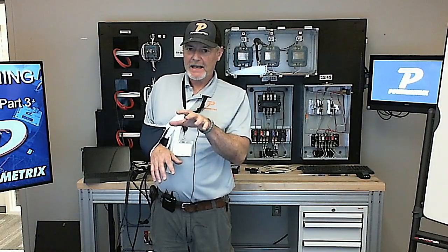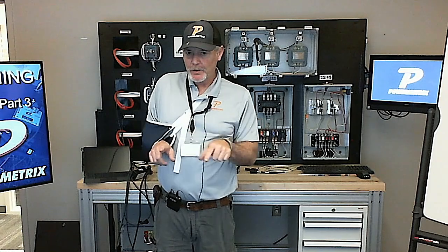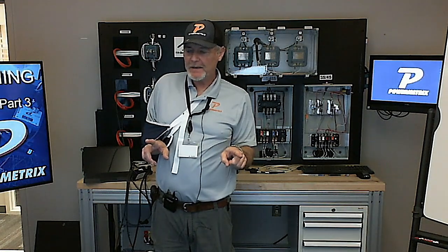So this is what we deal with on these deltas and these wye sites, these deltas and stuff. In this case, we were looped through opposite directions. We had only 2 CTs - we had 3 voltages, 2 currents, so we only had 2 CTs up there. So we had the 2 conductors from A and B phases running opposite directions through there.